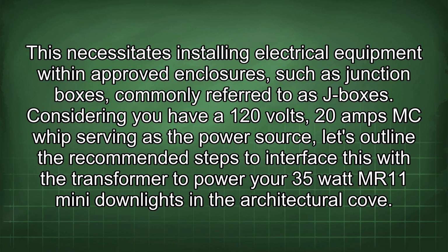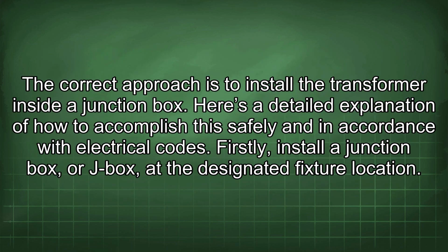Considering you have a 120 volts, 20 amps MC whip serving as the power source, let's outline the recommended steps to interface this with the transformer to power your 35 watt MR11 mini downlights in the architectural cove. The correct approach is to install the transformer inside a junction box. Here's a detailed explanation of how to accomplish this safely and in accordance with electrical codes.